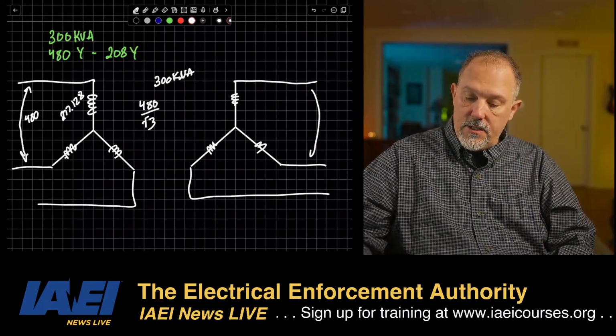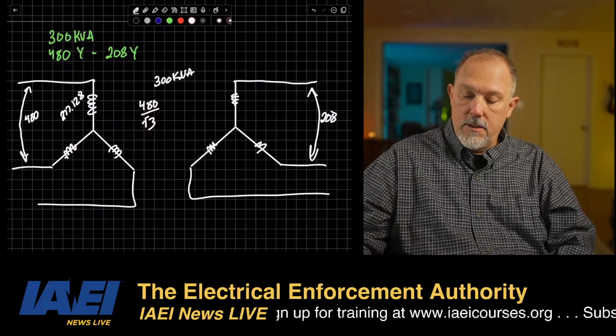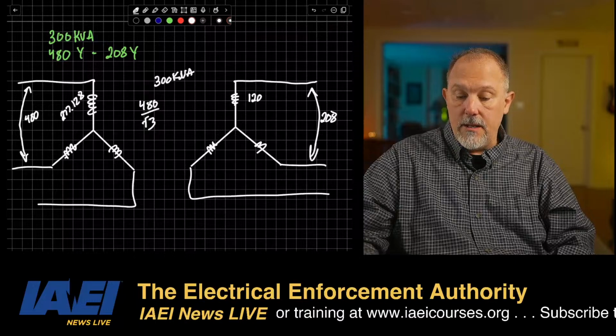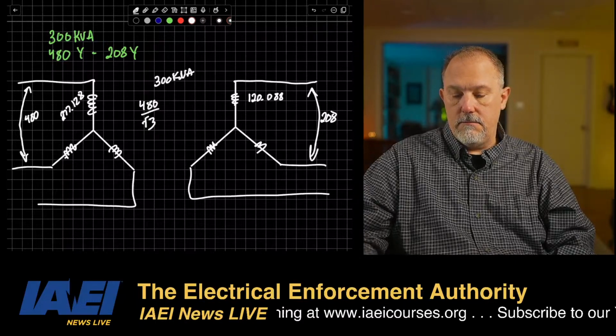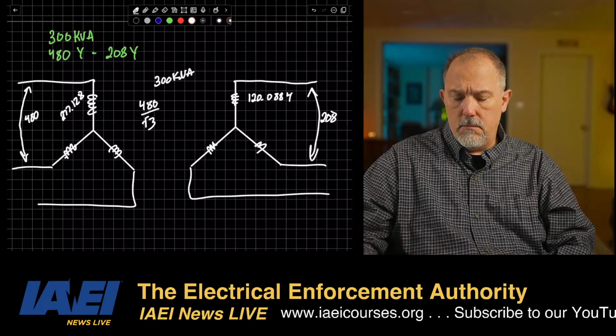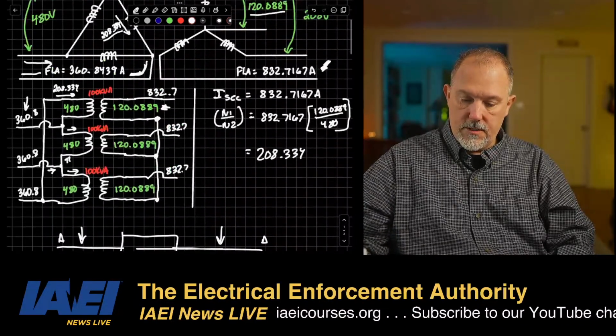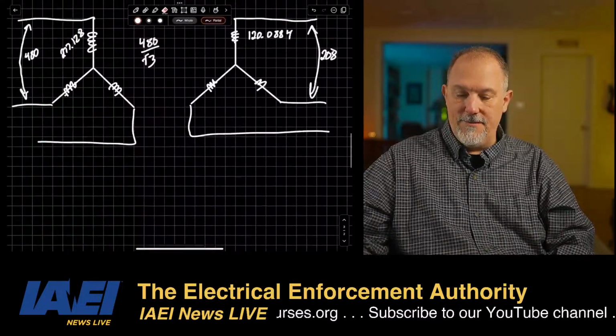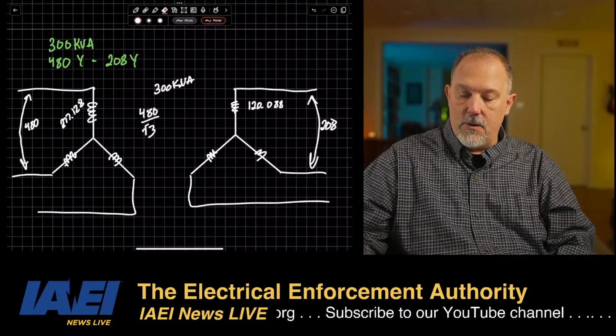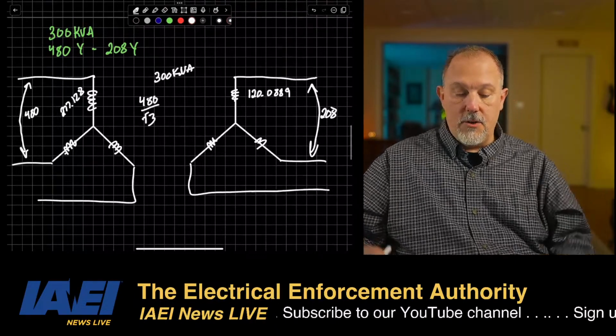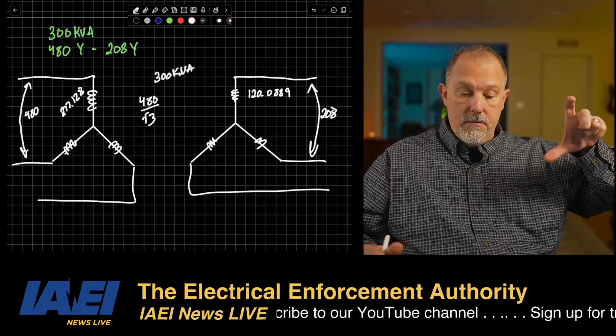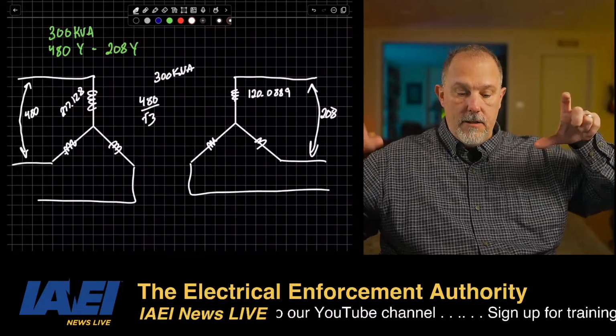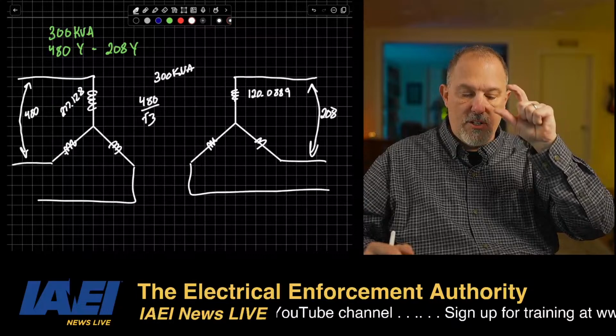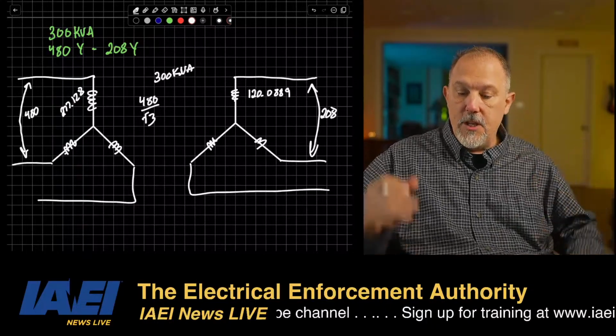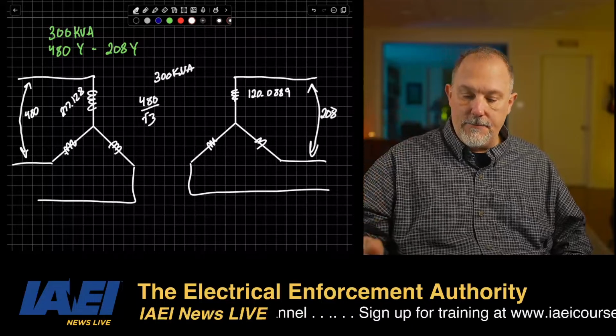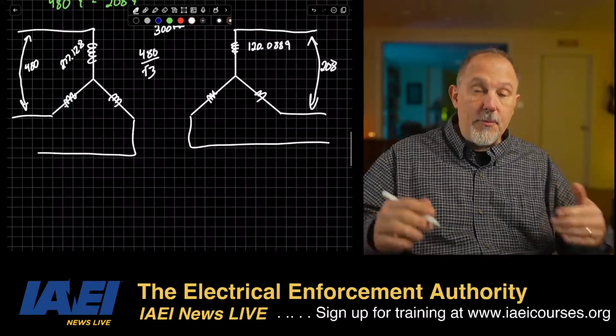And if this is 208, we already know this is 120.0889. So 480 line to line on the primary, 208 line to line on the secondary. My line to the center point neutral is 277.128 on the primary, 120.0889 on the secondary. And I know I have 300 kVA.